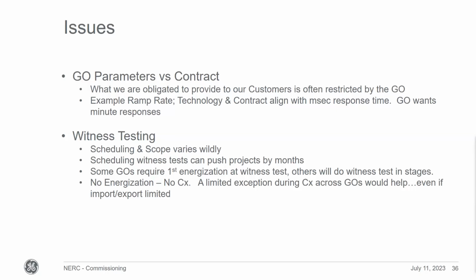No energization means no commissioning, right? Commissioning is energization. So I think a limited exception, some kind of self-witness process across grid operators, would help, even if limited. So those are the two main interconnection issues we see. I'm trying to keep this simple and not give too many examples of how often we run into these issues, but it's a lot, and it can slow things down.